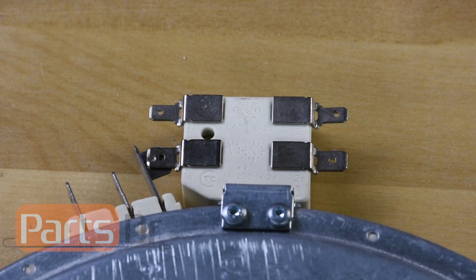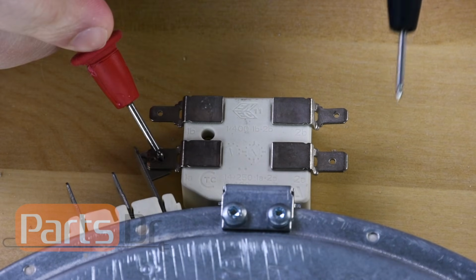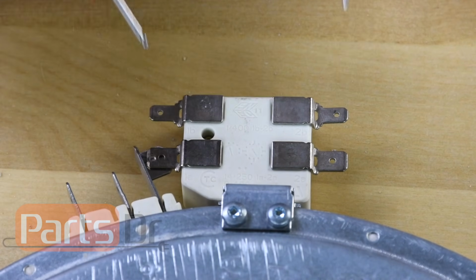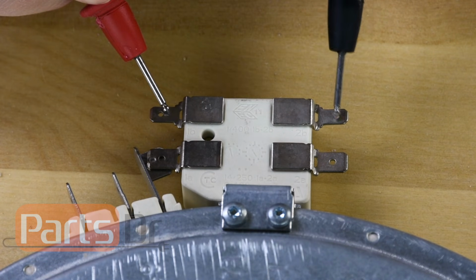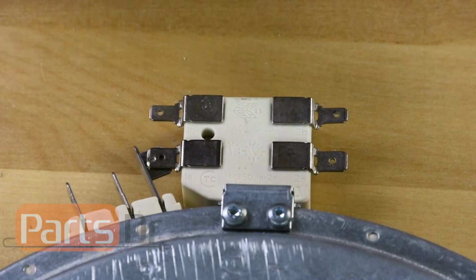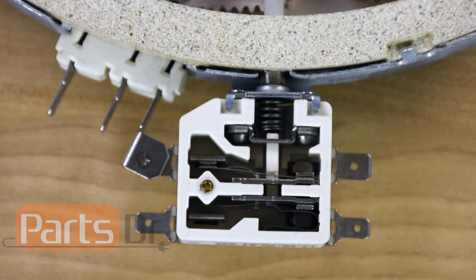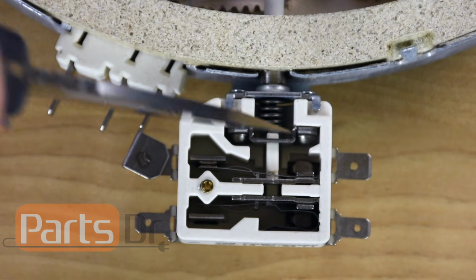To test the limiter at room temperature, you can do a continuity test between terminals 1A and 2A and terminals 1B and 2B. At room temperature, terminals 1B and 2B should have no continuity, and terminals 1A and 2A should have continuity. Here I have the cover taken off a limiter to show you how it works. When the probe heats up, it expands and pushes a switch arm that makes and breaks the electrical contacts inside the limiter.